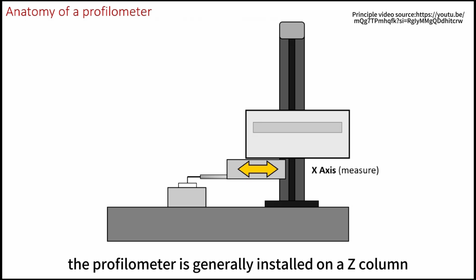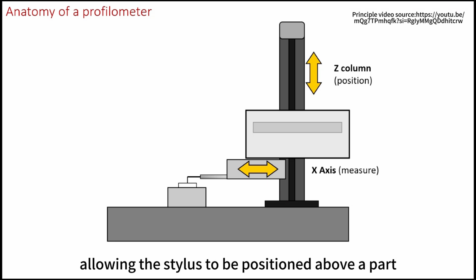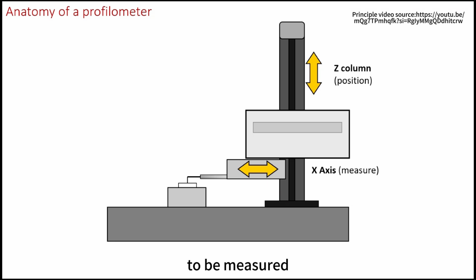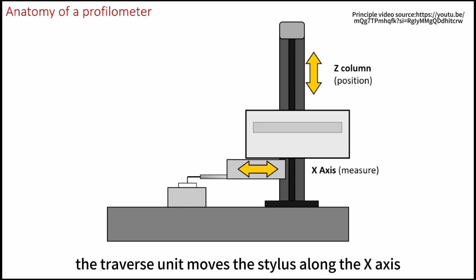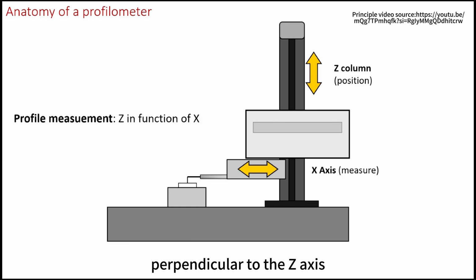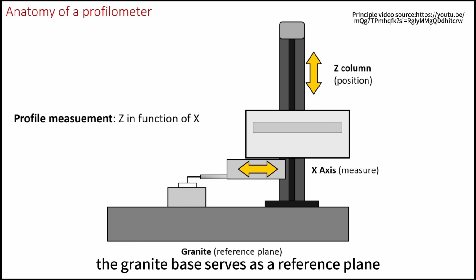The profilometer is generally installed on a z-column, allowing the stylus to be positioned above a part to be measured. The traverse unit moves the stylus along the x-axis, perpendicular to the z-axis. The granite base serves as a reference plane, and as a support for the parts to be measured.